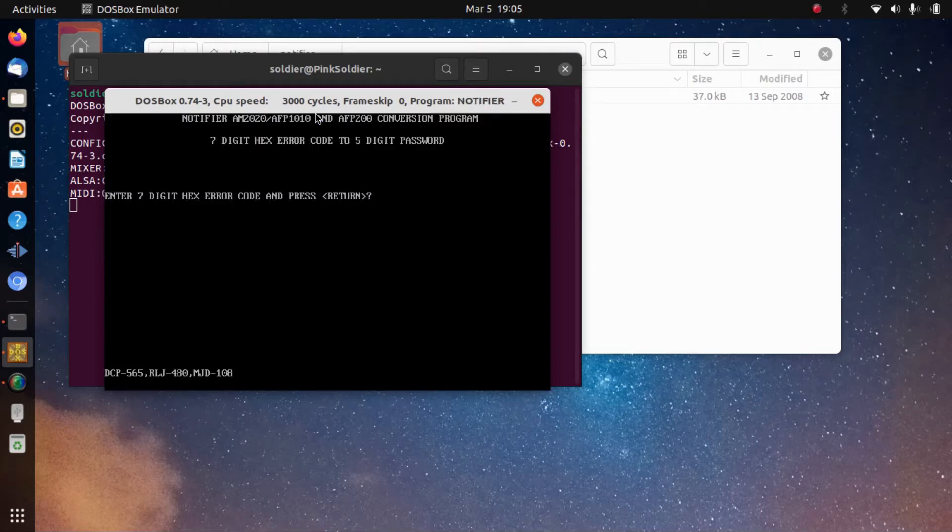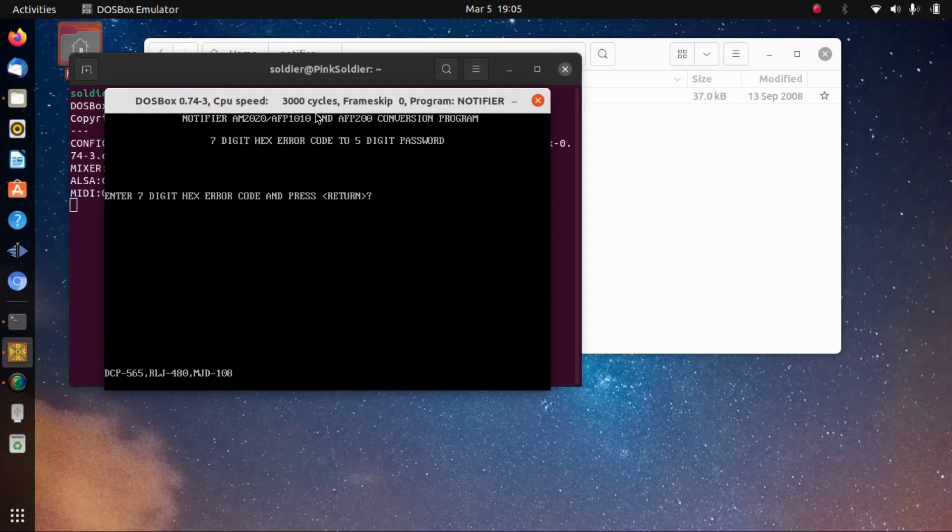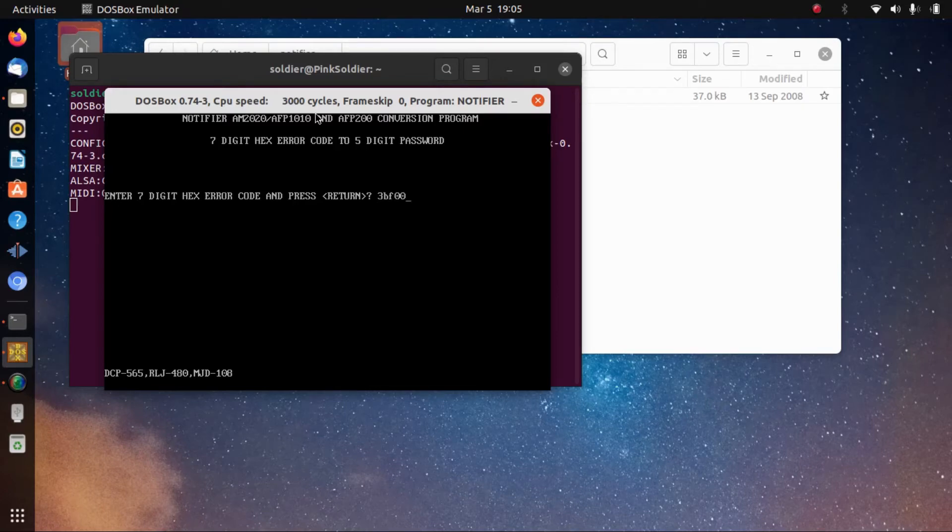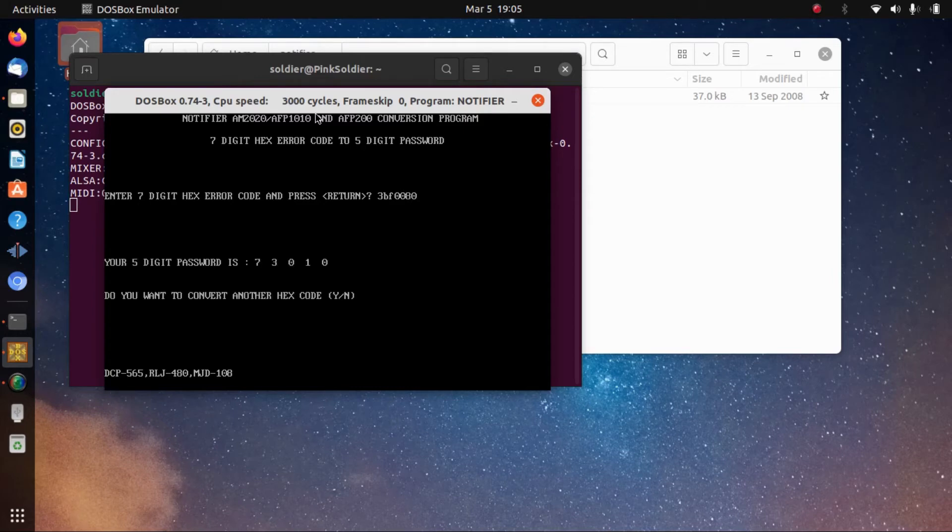Now we're gonna run a program called notifier.exe. The error code we got from the panel, from that 2020, was 3BF0000. Hit enter and you get 73010. So let's plug that into the 2020 and see if it works.